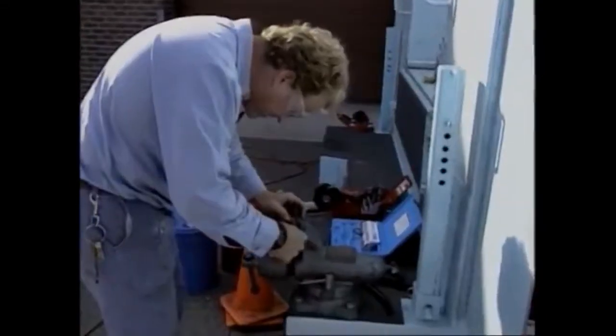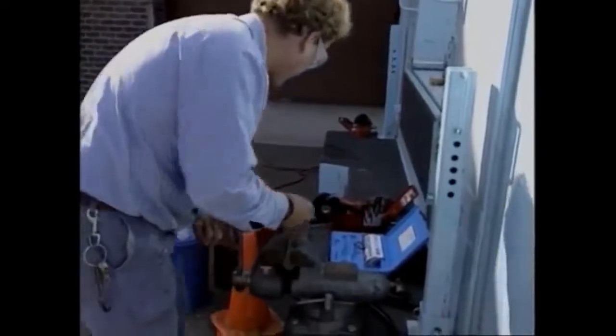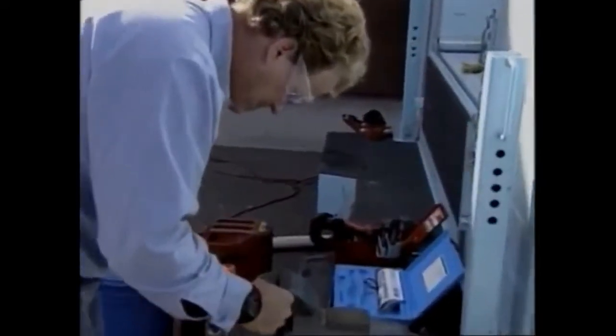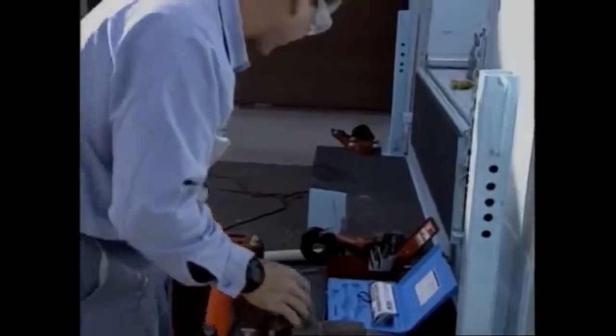Drawings need to reflect all modifications made to the station or force main. All drawings and plans must be kept up to date to facilitate future work and to evaluate station performance. It's especially important to have a written report detailing any unusual conditions or repairs made to the lift station. These reports should indicate how repairs were made, time required, unusual conditions encountered, special equipment or materials needed, or additional maintenance scheduling required in case the job needs special attention or must be repeated in the future.